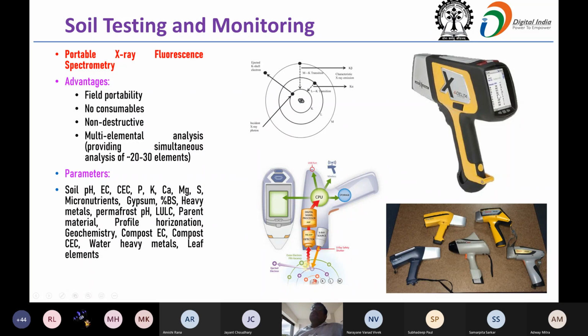Now, what are the benefits of this instrument? It is very lightweight, only 1 kg, and it is portable, so field portable. It requires no consumables like the traditional methods. It is non-destructive. That means if you have a very small amount of sample, in the traditional method the sample gets lost during the digestion process, but in this method you are not destroying the sample. And it does multi-elemental analysis with high throughput, giving you the results of 20 to 30 elements within only 60 to 90 seconds.